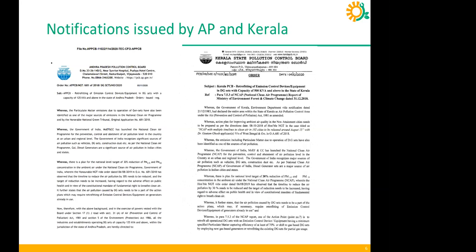Therefore, this particular difference you will see a little here and there in the policies that the states are laying out. However, the fundamental remains the same: what should be a retrofit, what minimum PM reduction efficiency that retrofit should be giving to you, that is 70%, and from where it should be tested, that is any one of the 5 CPCB recognized labs, and under what standard, ISO 8178-4 (D2 cycle) for an equivalent kVA. That means if you have a 500 kVA and I am a vendor who is coming out for providing you a retrofit control equipment for your diesel generator that is 500 kVA, I need to have a 500 kVA test report from any one of the 5 CPCB recognized labs, even if I come and sell the product to you. That is what the premise of the entire policy is.